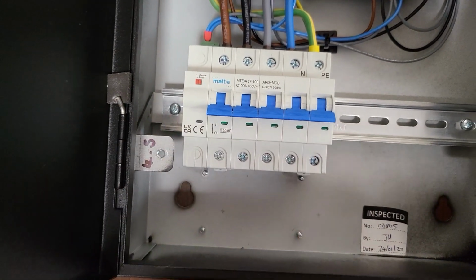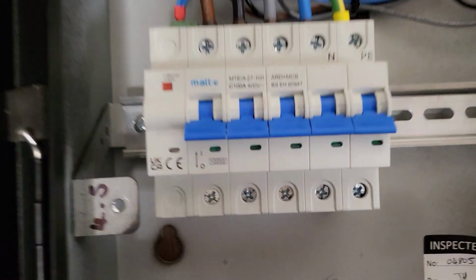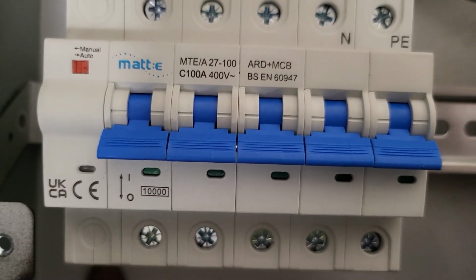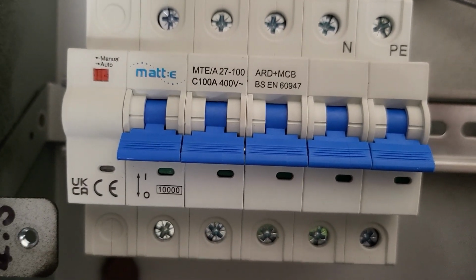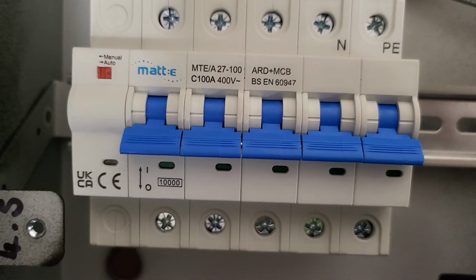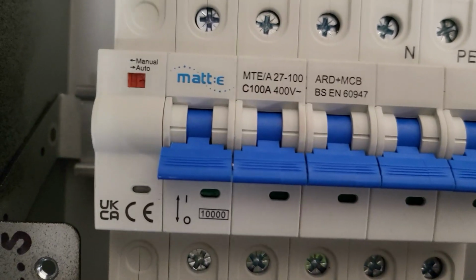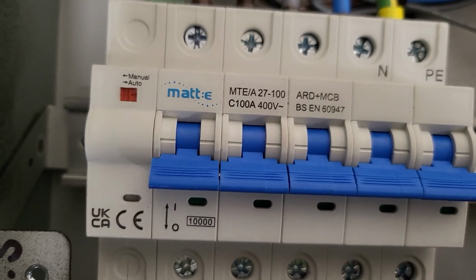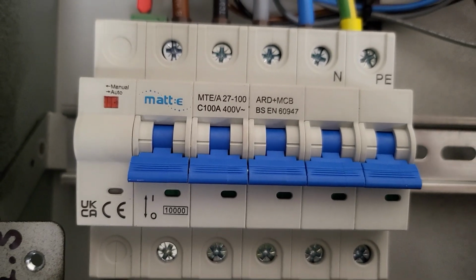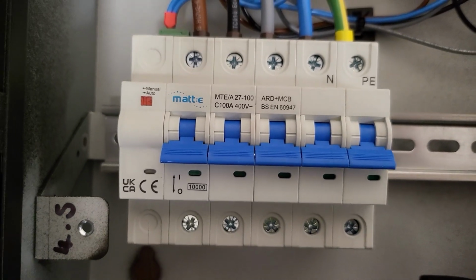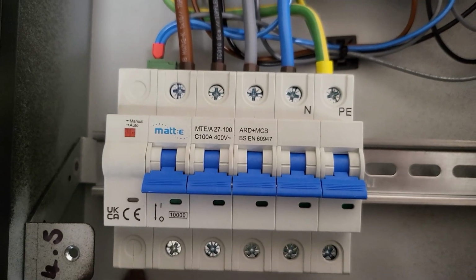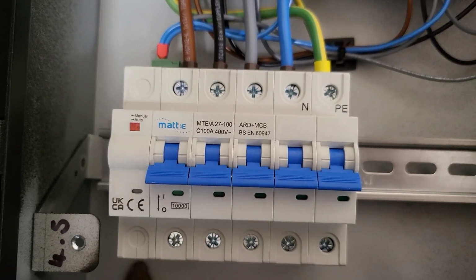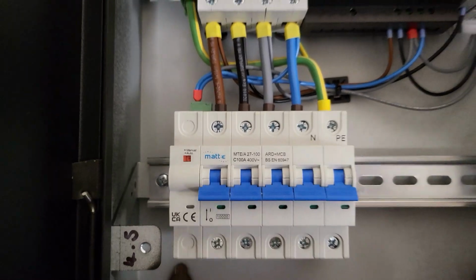connection point for your outgoing circuits to the load, and we'll speak a bit about what this does, but you can see on there it is a 60947 ARD plus MCB, and you can see there it's got manual and auto reset. This is the manual reset variant. Matt E have got a product out now that does auto reset just the pen fault detection, none of the other gubbins, and we'll speak about that when we're looking through the manual.